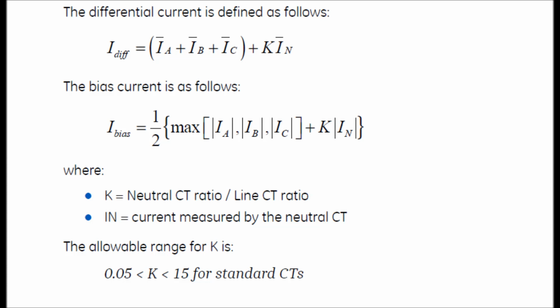So all the CT inputs are taken at the same base value. So the factor K is implemented, and IN is the current measured by the neutral CT, and the allowable range for K is 0.05 to 15 for standard CT.